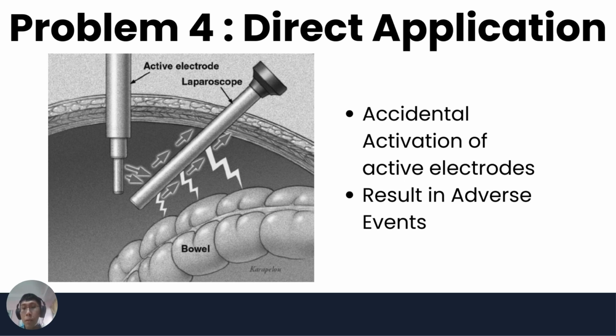The second most common type of electrosurgical injury occurs when the active electrode is energized accidentally while in contact with non-target tissue. Most of these injuries are due to inappropriate placement of the active electrode on the patient between uses and activation of the unit by unintended pressure on the hand switch or foot switch. Another cause is ESU component failures, such as issues with the active electrode, hand switch, or pencil, and activation of other electrodes.